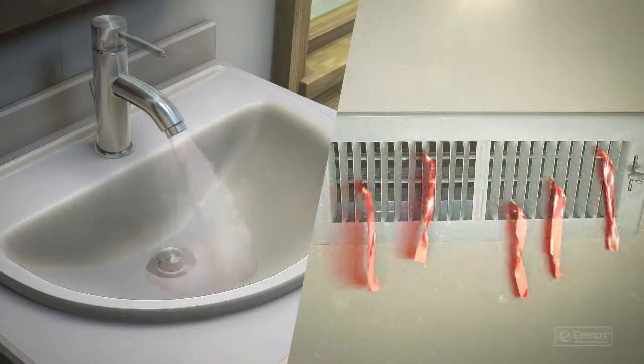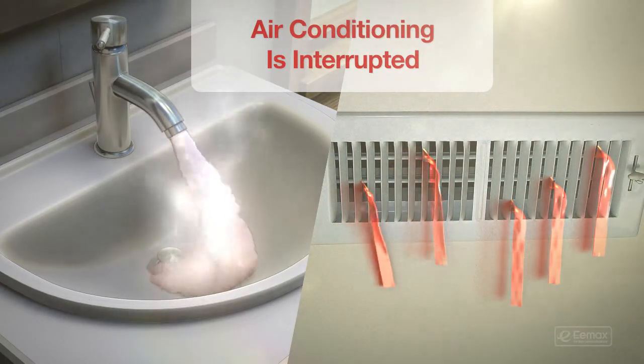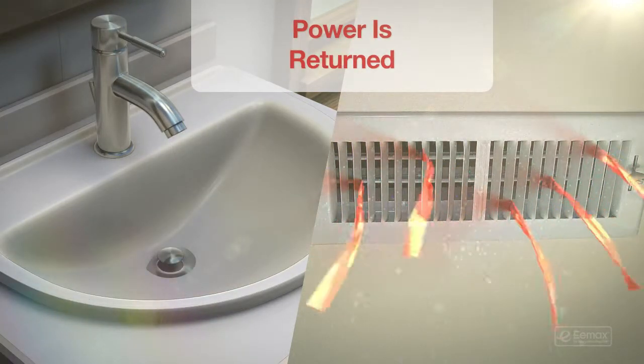Here's how it works. When your Eemax electric tankless water heater needs power to work, power to a non-priority load — like air conditioning — is interrupted. When the need for hot water is over, power is returned to the interrupted load.